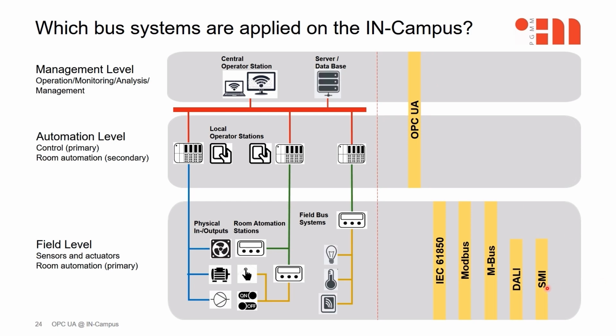The field bus systems used are SMI for blinds, DALI for lighting systems, MBus for meters, Modbus for devices and systems, and lastly IEC 61850 for electrical systems. The main difference, however, is the use of OPCUA instead of BACnet for the communication of the automation and management level. I will go into the reasons for this at a slightly later stage.